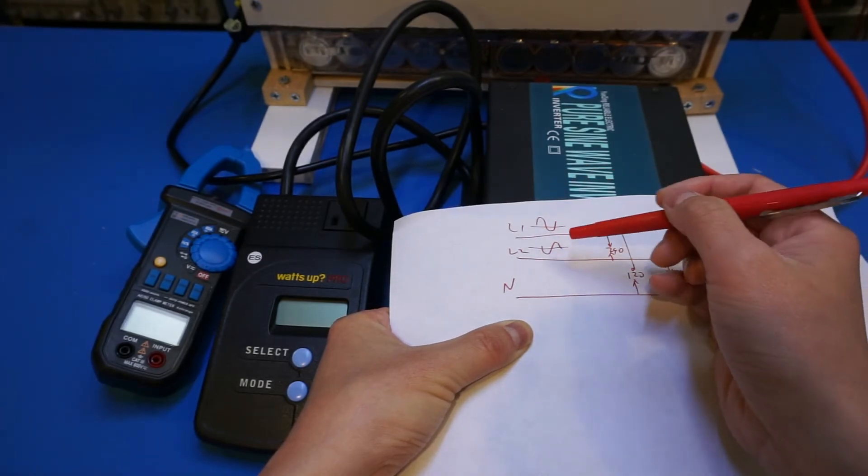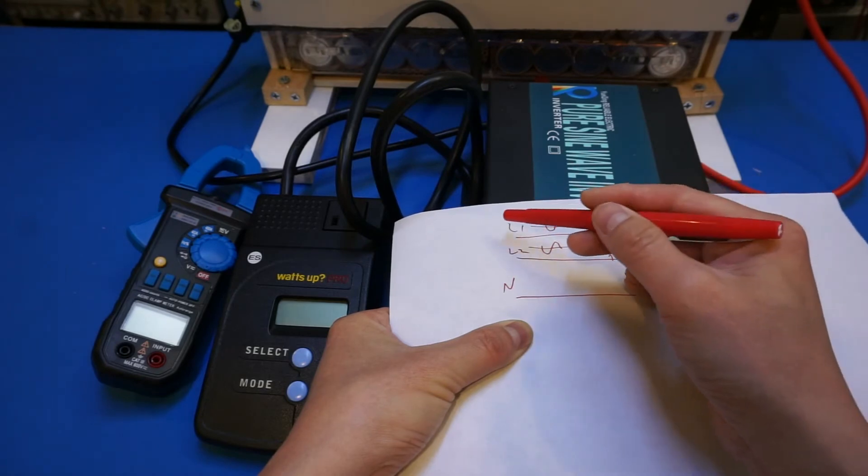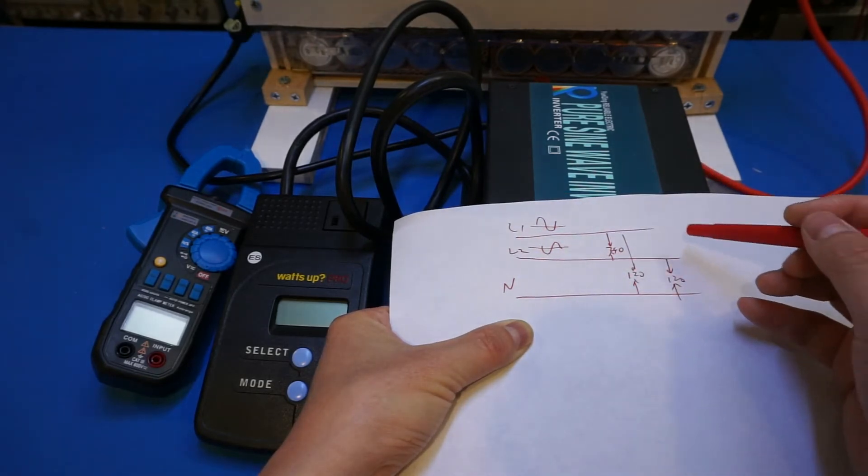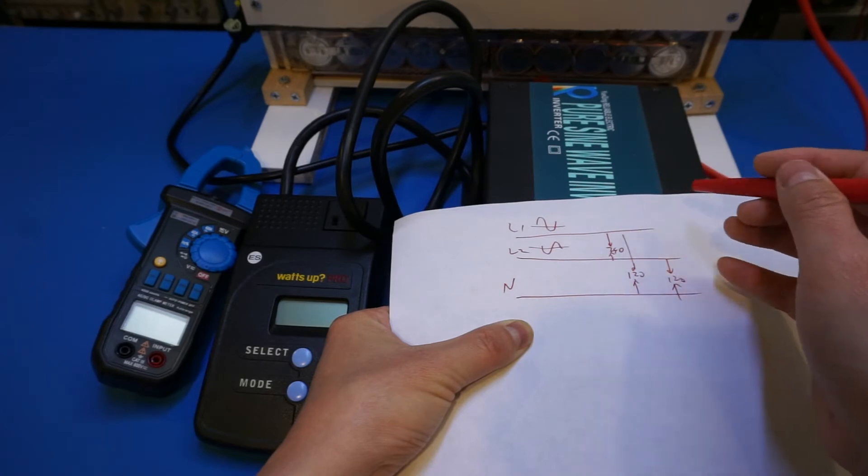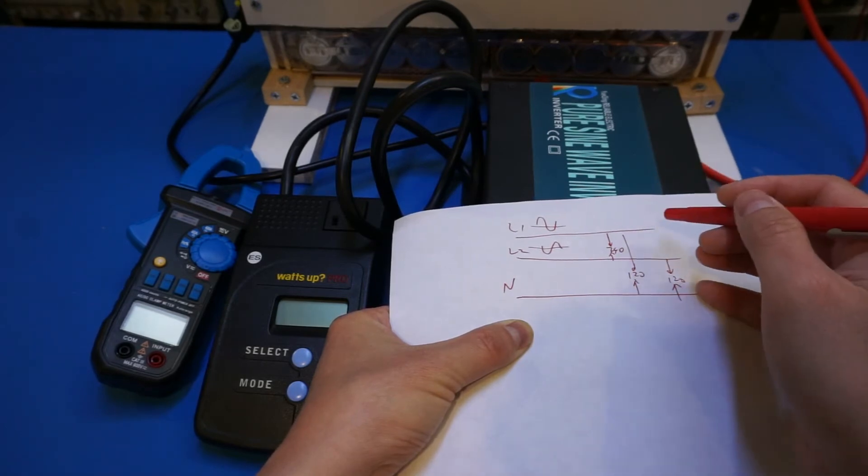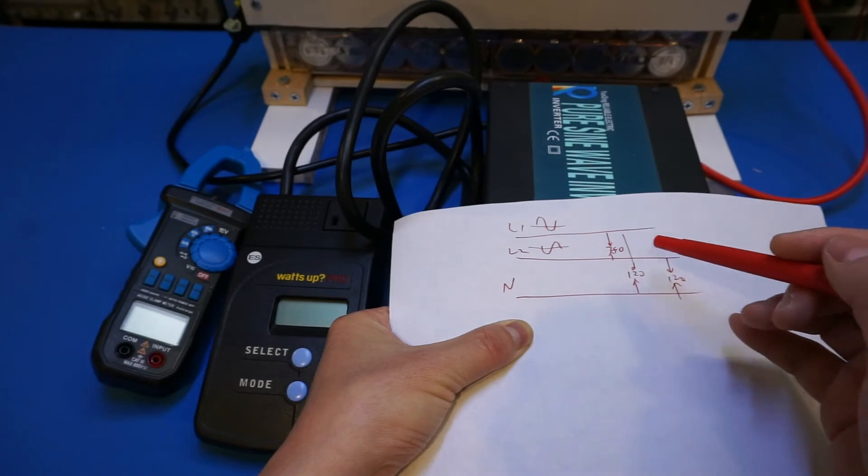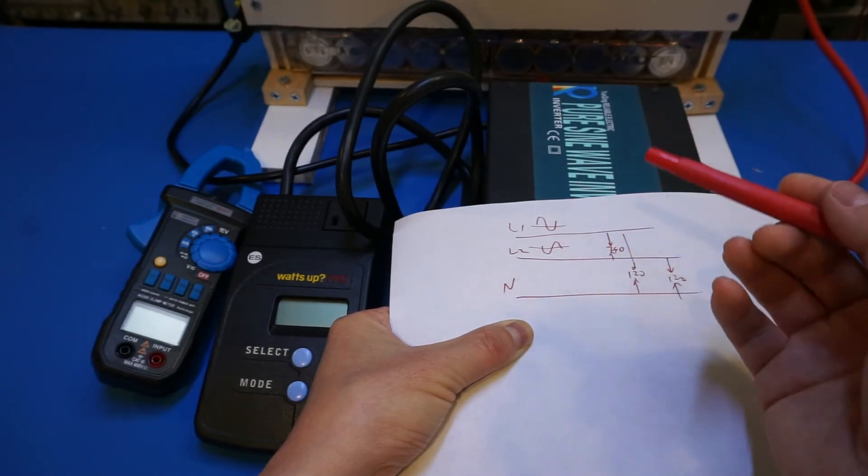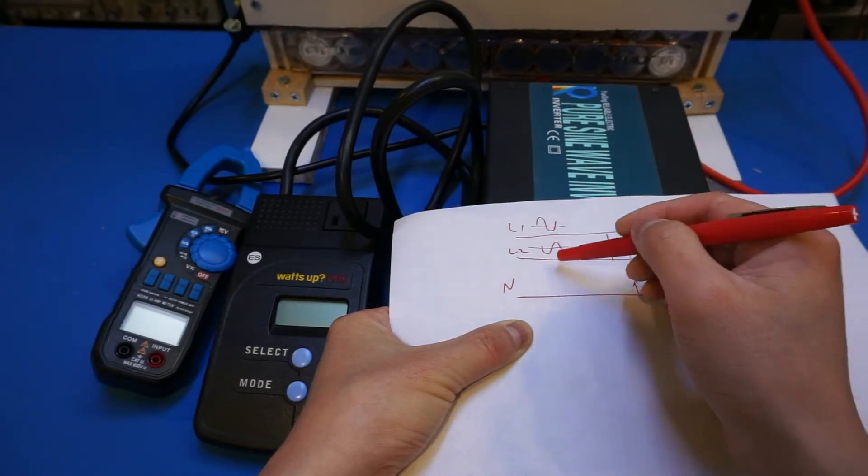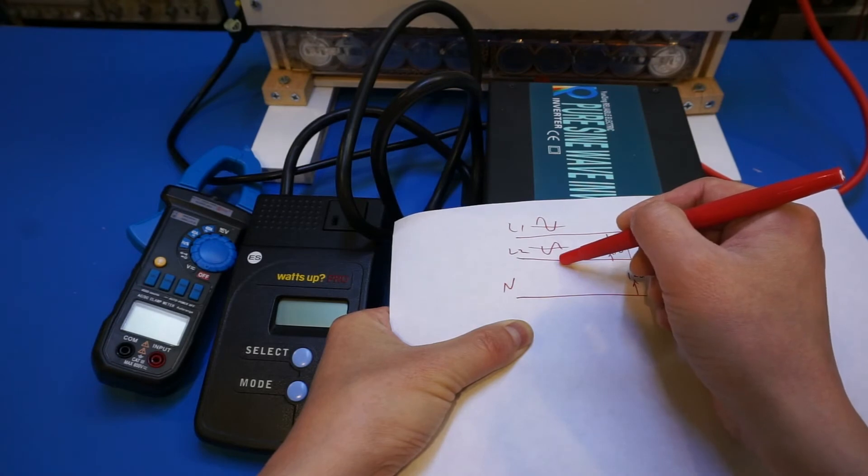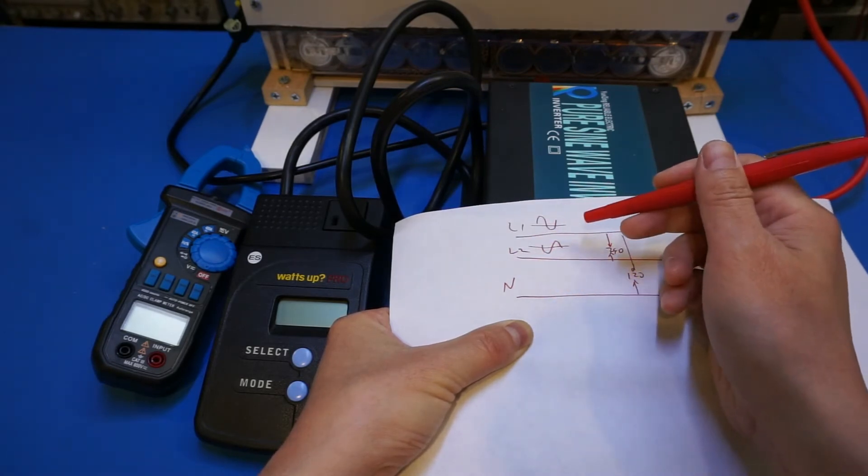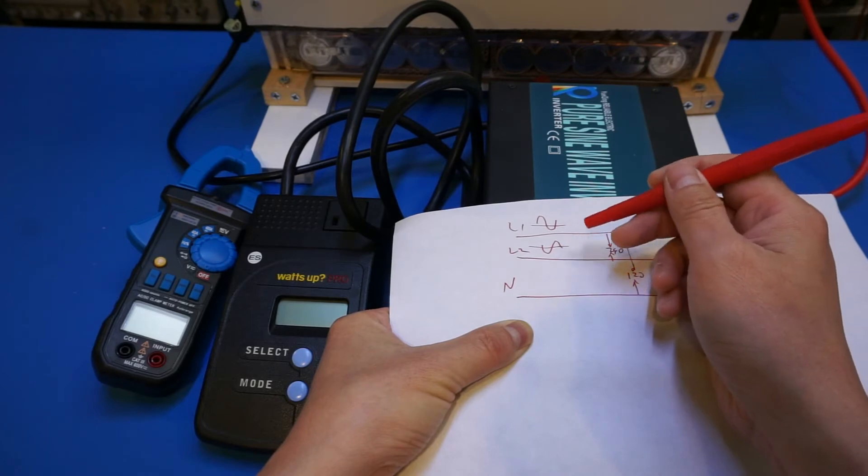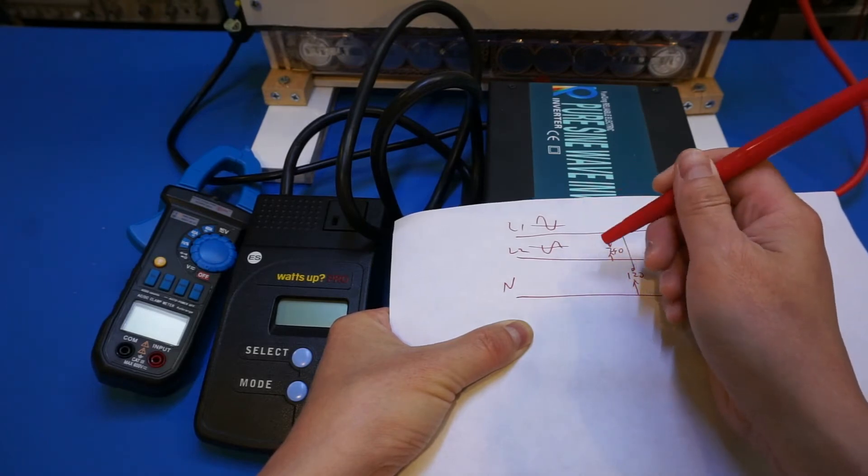This is totally safe to do because everything running on 120 will still see the 120 volts and the desired voltage for them to work. And for appliances that are running on 240, as you will see here, they simply just would not work because these two lines are essentially tied together. They would just be a zero volt across them, so they would just not work instead of having problems.